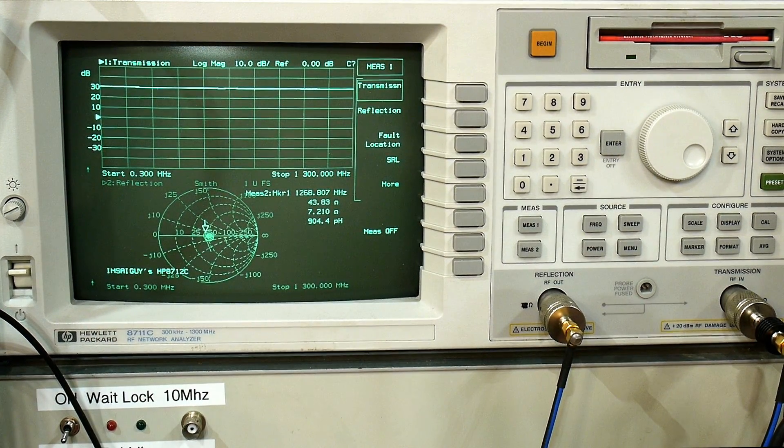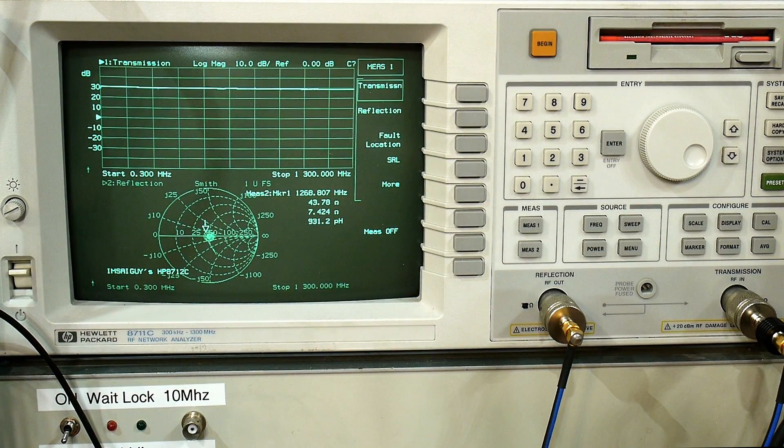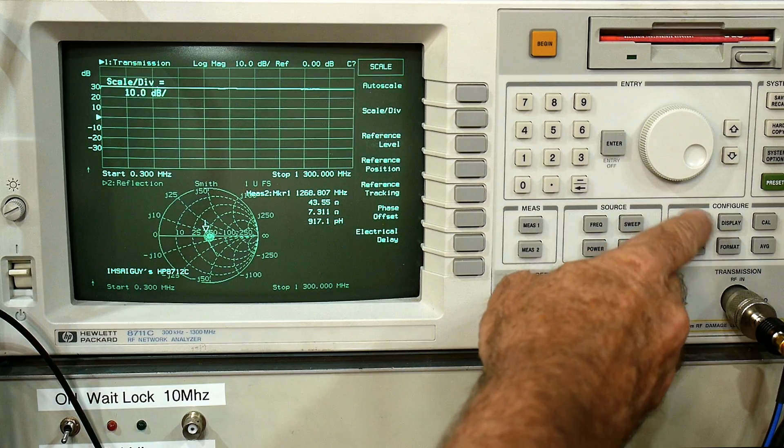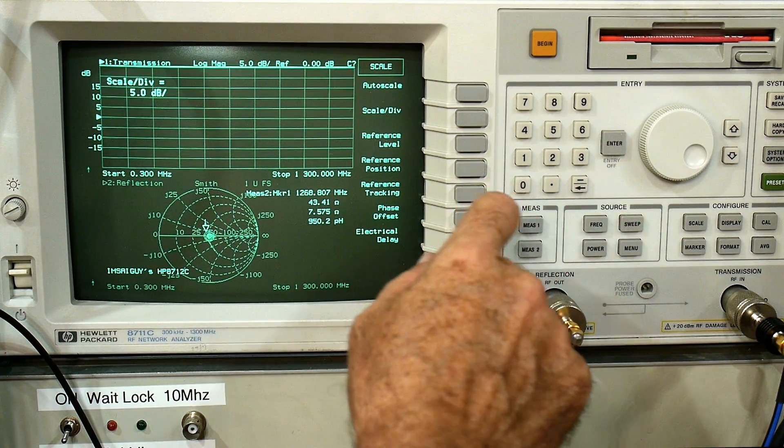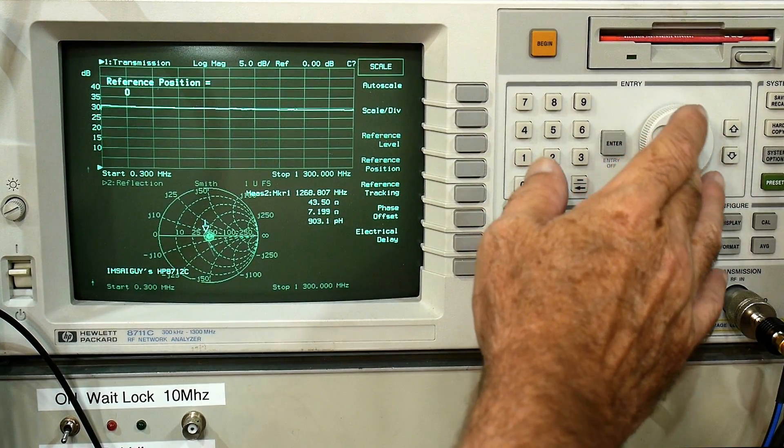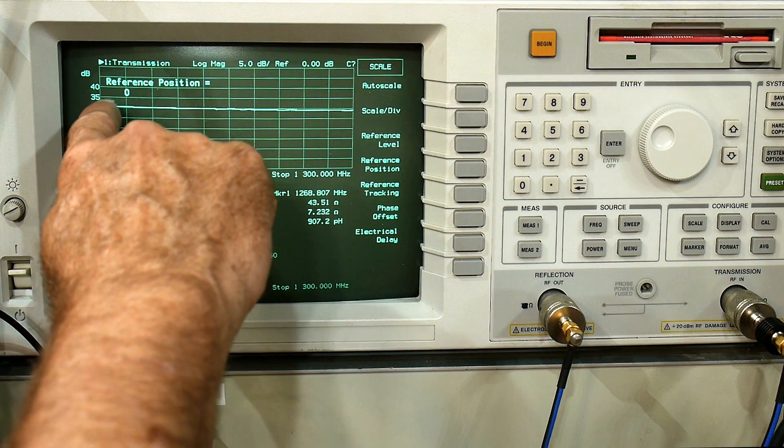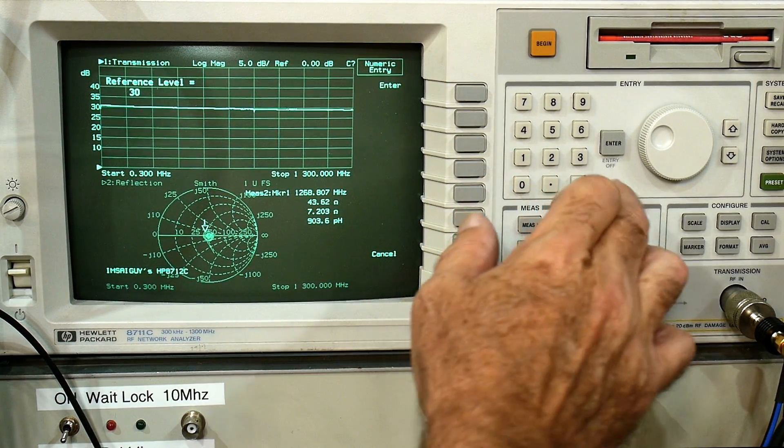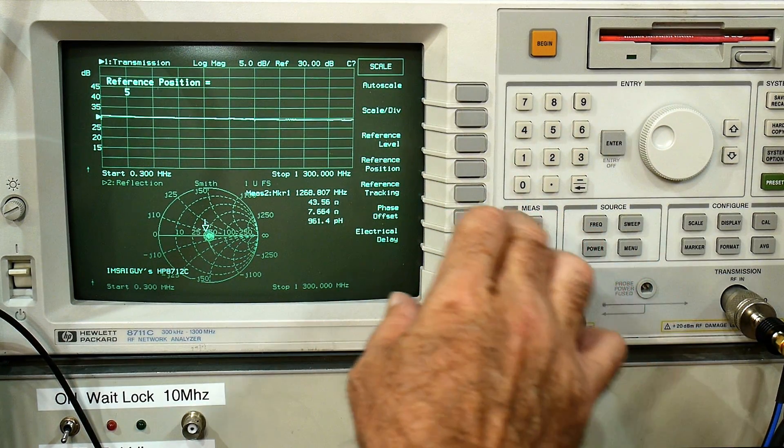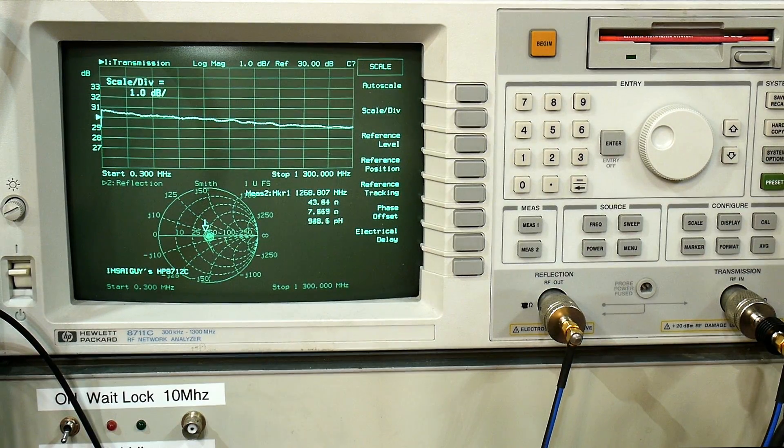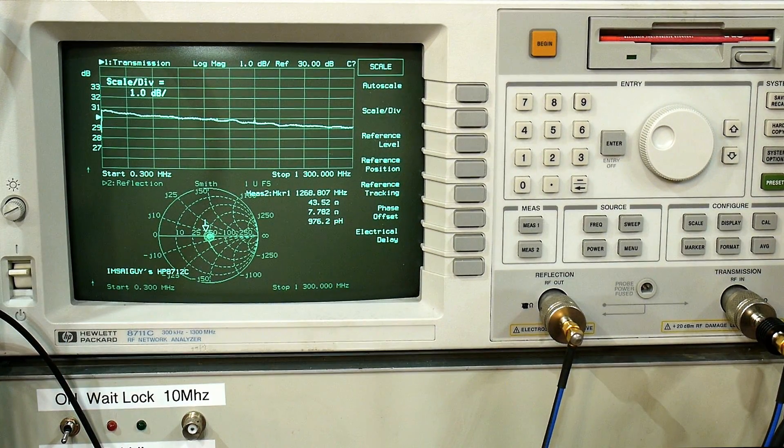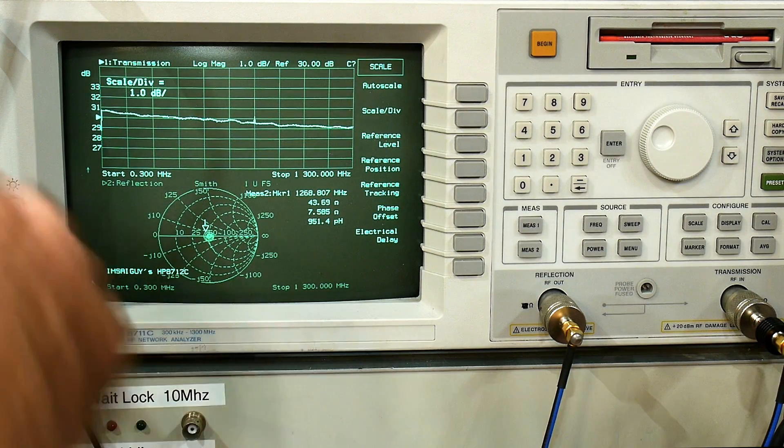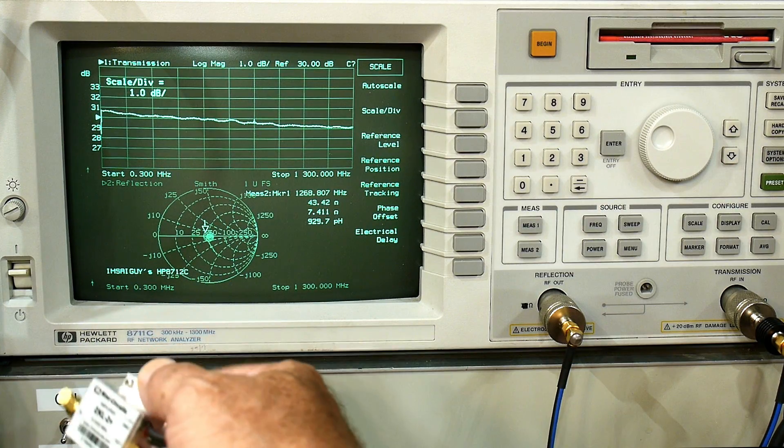Let's go back to measurement one and we are getting 30 dB out. So it is a 30 dB amplifier. Let's change the scale here to be a little bit nicer. Pretty much 30 all across. Let's do reference level of 30, reference position of five, and scale per division of one. Yeah, it's certainly within a dB and pretty flat, not many wiggles in it. Looks really really nice.